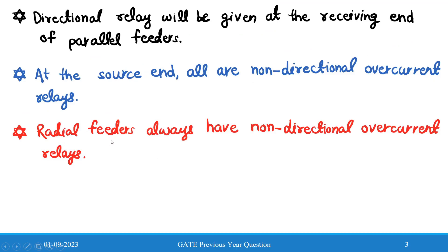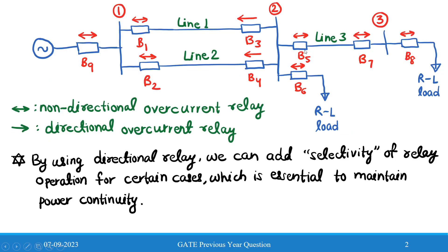The third point is that radial feeders always have non-directional overcurrent relays, provided there are no active sources. Line three is a radial feeder, so all relays corresponding to it are non-directional: R5, R7, and R8 will be non-directional overcurrent relays. R6 will also be non-directional because the load is passive and cannot reverse the current.